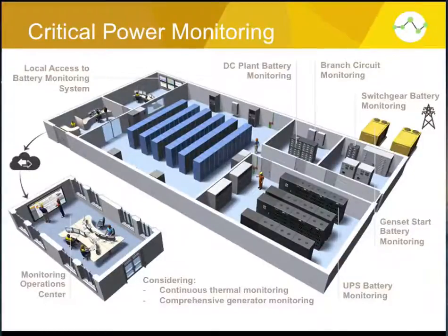We monitor switchgear, we monitor genset start battery monitoring. A lot of people don't know it, but the number one reason a generator fails is a bad start battery, and very often those generator batteries are subject to harsher environmental conditions, so they actually need to be monitored more carefully than inside plant.